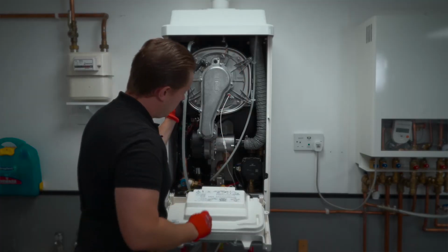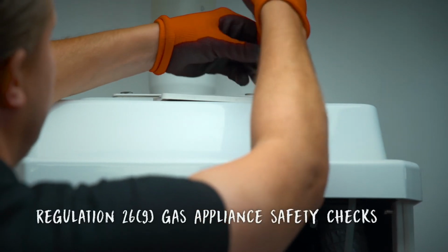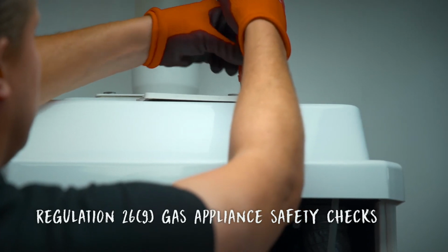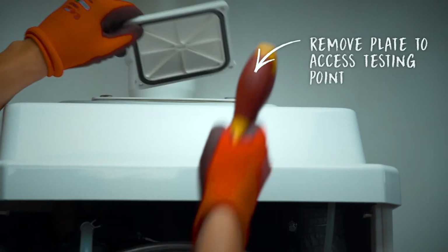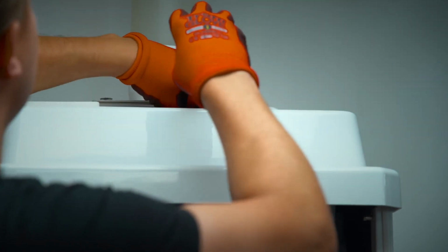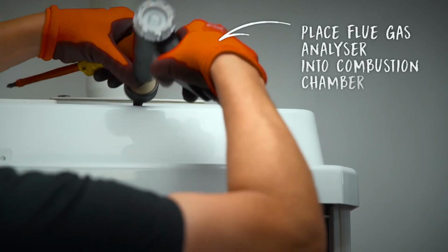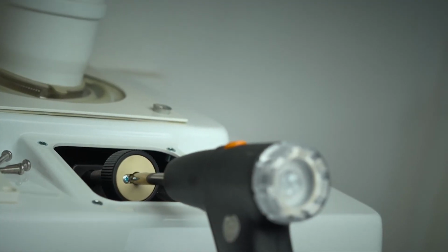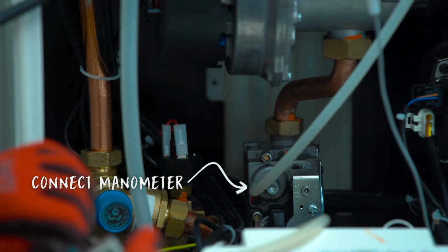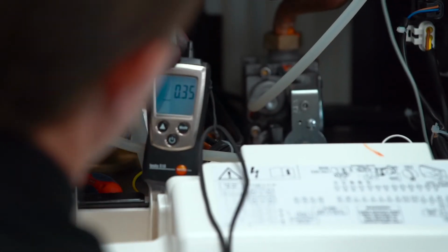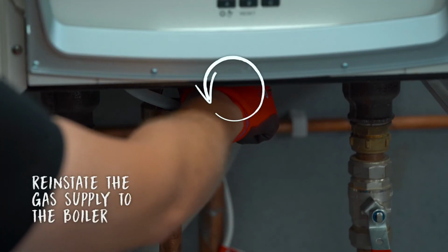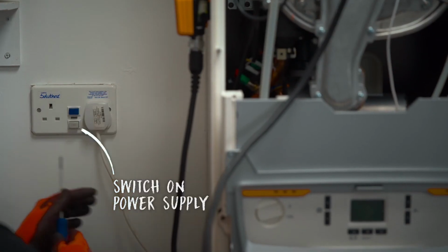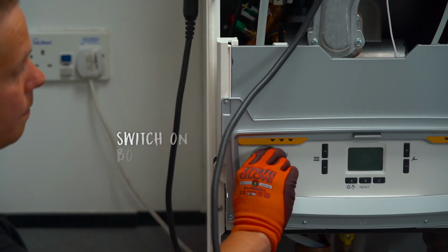It is next crucial that Regulation 26(9) gas appliance safety checks should now be carried out. To do so, first remove the flue hood cover to access the flue gas analyzer test point. Place a calibrated flue gas analyzer into the combustion chamber and connect a manometer to the inlet test point of the gas valve. Reinstate the gas supply to the boiler and then the power supply before switching on the boiler.